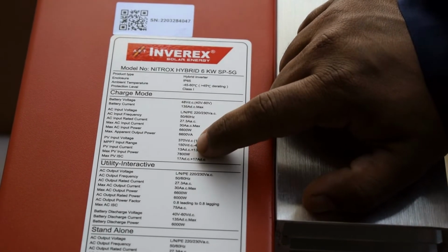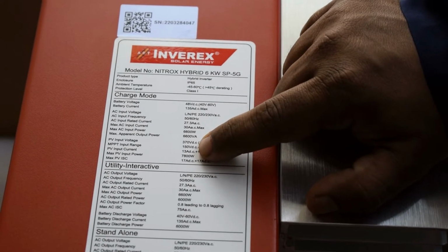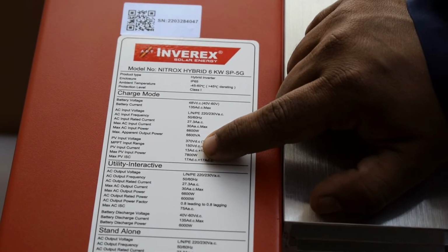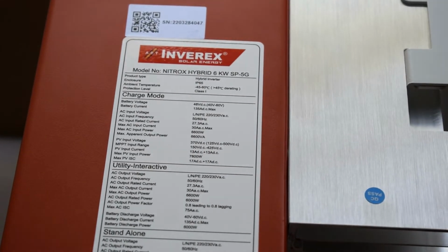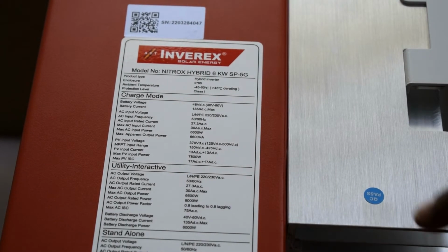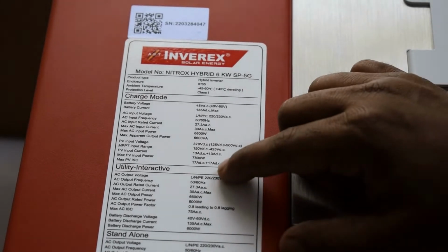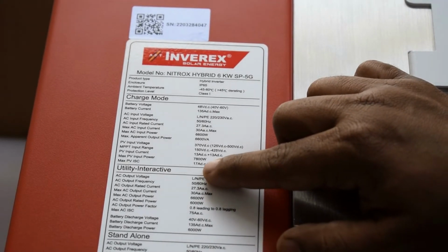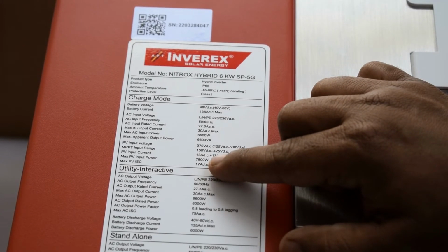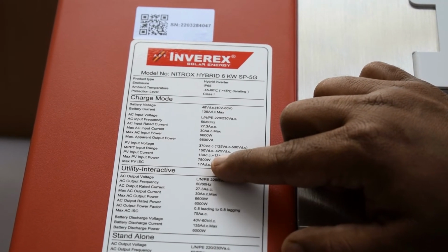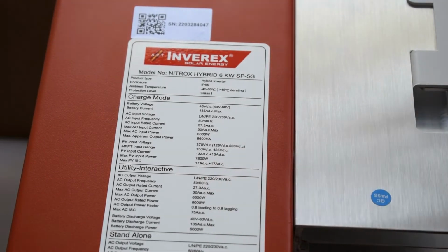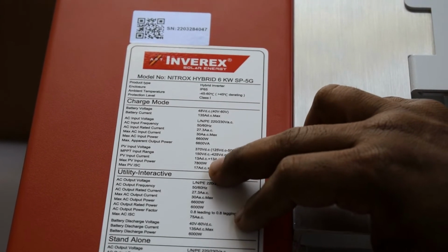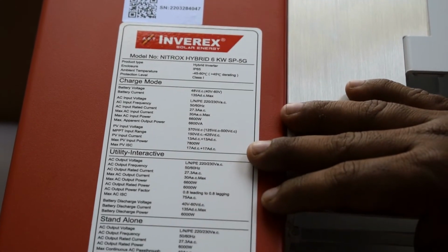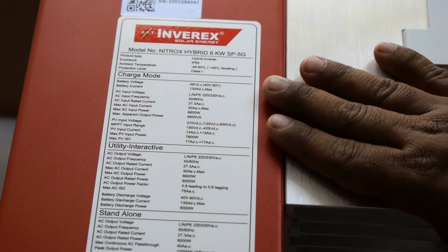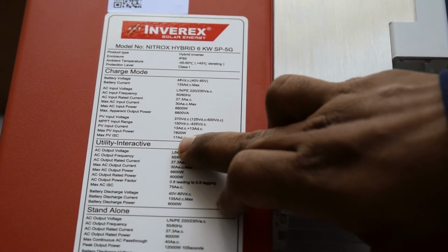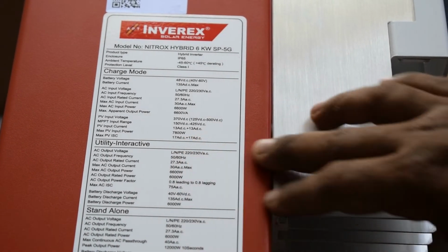So we can only connect medium range panels, 13 ampere, with this inverter. We cannot connect the Trina 650 or 590 panels. The maximum input power of solar is around 7.8 kilowatt, so we can connect around 8 to 9 kilowatt of solar panels, and we can get a maximum of 7.8 kilowatt in Karachi. The maximum PV short circuit current can go up to 17 ampere.